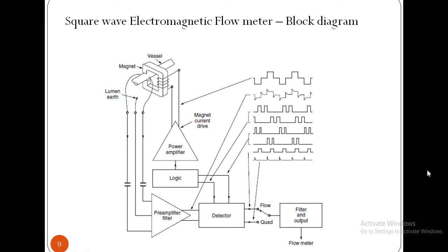A phase-sensitive detector is used to recover the signal, which is an analog of the flow rate being measured. The demodulated signal is given to an active RC low-pass filter, which provides a uniform frequency response and a linear phase shift from 0 to 30 Hz. This is followed by an integrator circuit to provide an output corresponding to the mean flow. The output signal thus obtained can be put to a recorder to read the blood flow rate from the calibrated scale.